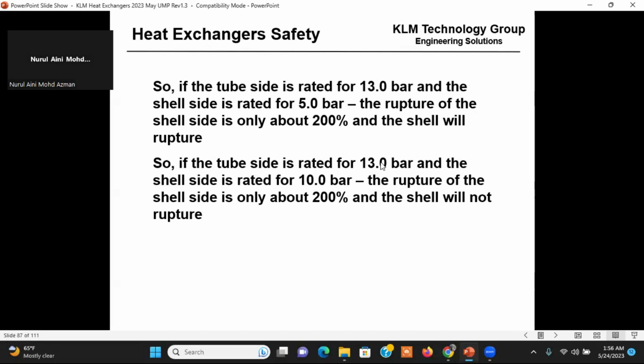If the tube is rated for 13 bar and I rupture the tube and it's 10 bar, I don't necessarily rupture the shell side. And so if it's 13 bar and the shell side's rated for 5 bar, if I rupture a tube, I can blow up the shell. If it's rated for 13 bar and the shell side's rated for 10 bar, I won't necessarily blow up the shell. Okay. And so I like this 10/13 rule because we only rate it for 200% of design. We design it for around 200%, and we do a hydro test to 120 or 130% of design. Okay. Now this is a rule. It's a rule I want to follow because I don't want to hear one day that one of my heat exchangers blew up because I didn't follow this 10/13 rule. And I'm already running out of time.